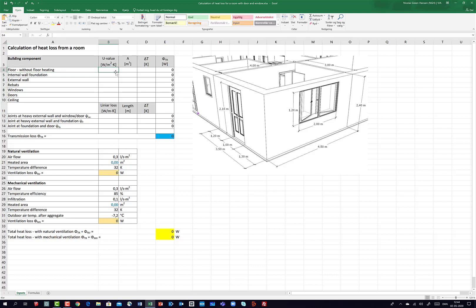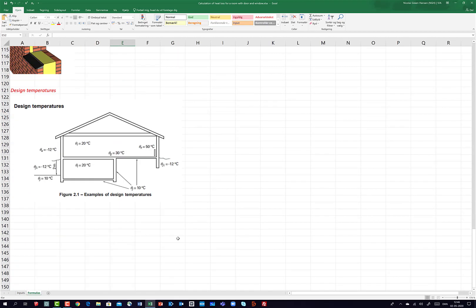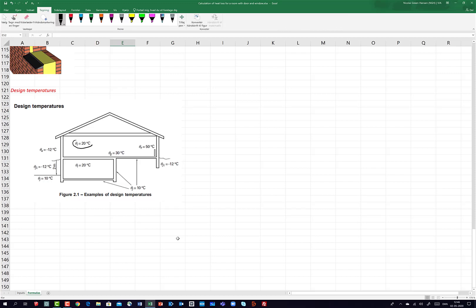The U-value I put in a fictive value 0.12. The area of the floor is 4 times 3 meters, so that is 12 square meters. Then I need to find the temperature difference. I go to the tab formulas and at the very bottom I can see the design temperature. For the floor, inside the house the temperature should be 20 degrees and the soil temperature is 10 degrees, so the temperature difference is 20 minus 10, which is 10 Kelvin. This is without floor heating.